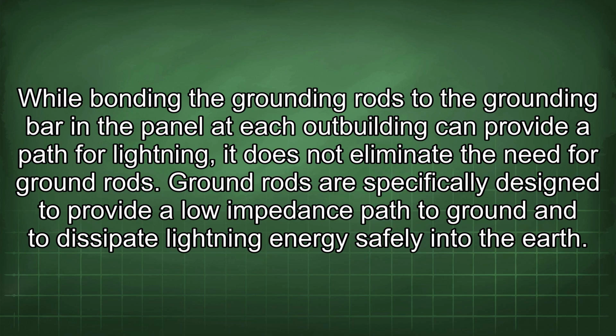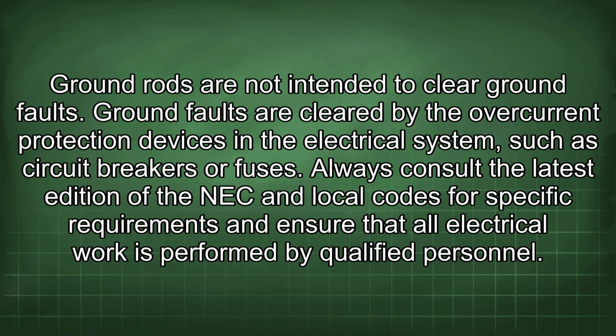Ground rods are specifically designed to provide a low impedance path to ground and to dissipate lightning energy safely into the earth. Ground rods are not intended to clear ground faults. Ground faults are cleared by the overcurrent protection devices in the electrical system, such as circuit breakers or fuses. Always consult the latest edition of the NEC and local codes for specific requirements and ensure that all electrical work is performed by qualified personnel.